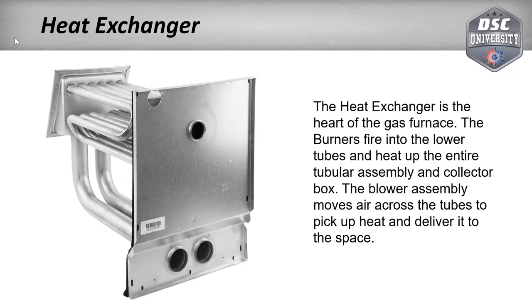Ruud's heat exchangers are great. They rarely ever fail, because of the way they're designed and made. They use some stainless steel components in them, though most of it's aluminized steel. There's not any mechanical fasteners, not any rivets or screws or anything that holds it together. It's swedge fittings, and you can see how the back of the collector box up there is crimped over.